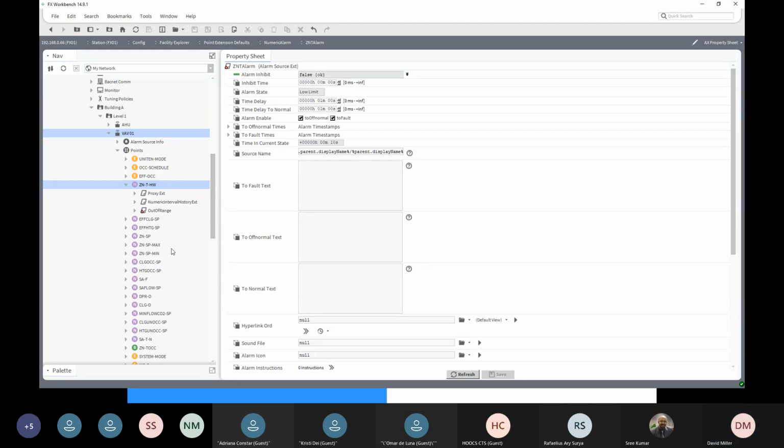So we're getting that point, that name, and that name together with a slash in between defines the point. Now, when your alarm comes up, you want to be able to identify it in the entire system. So you might want to go further, because VAV01 won't be unique. There'll be a VAV01 on level 1, and there's possibly a VAV01 on level 2, and so on.